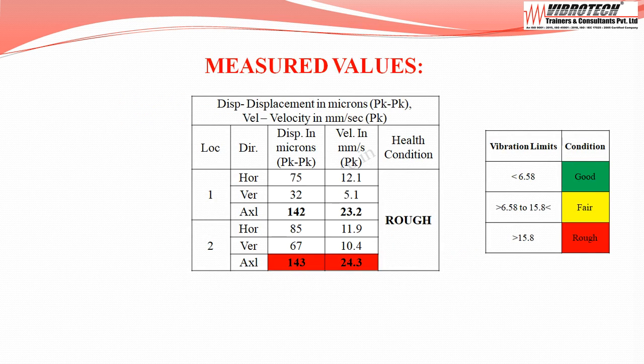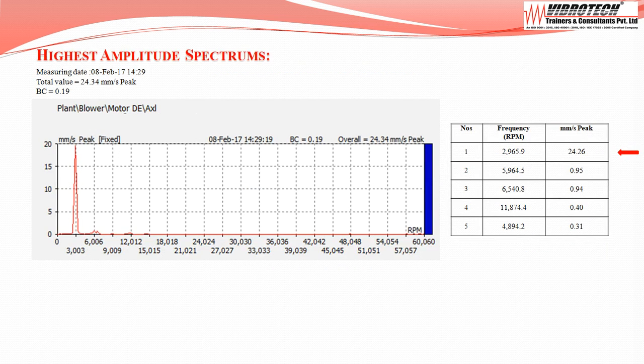The vibration values are maximum at the motor drive end in the axial direction, with velocity up to 24.3 mm/s peak and displacement of 143 microns peak-to-peak. The equipment falls under the rough category, with vibration levels exceeding acceptable limits.